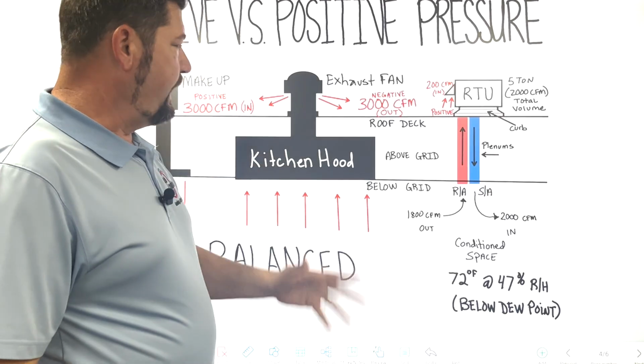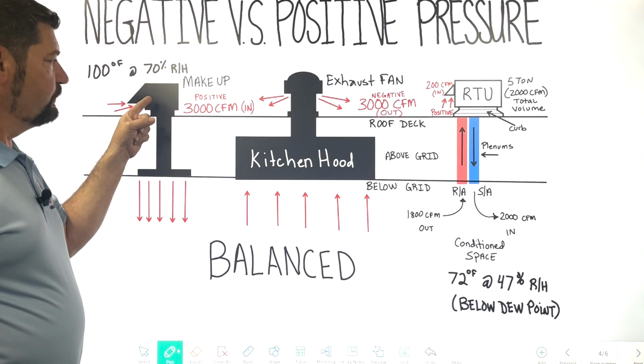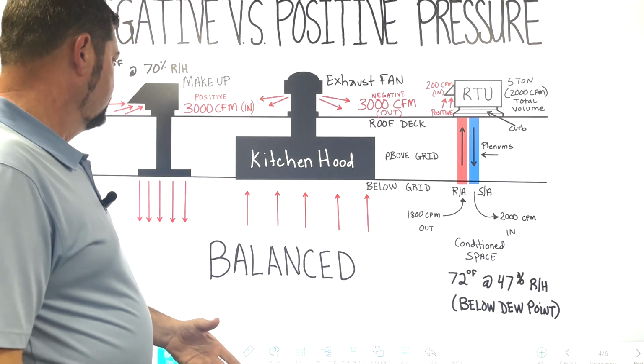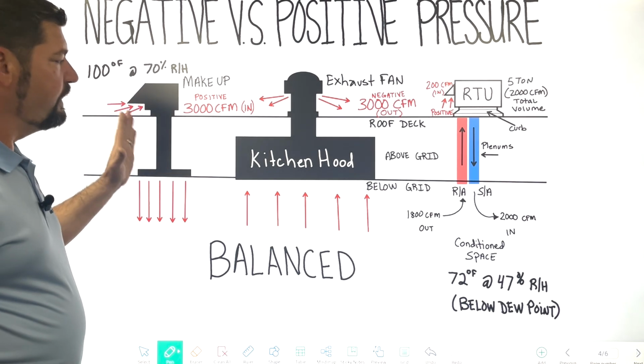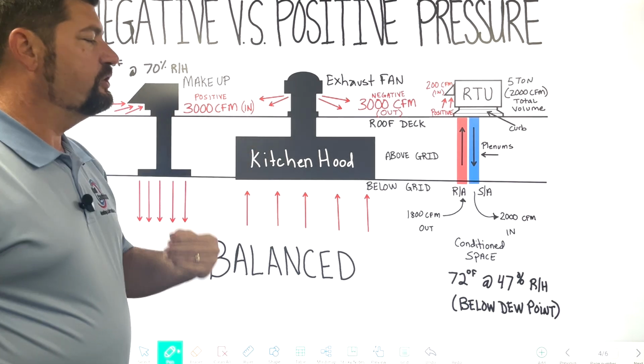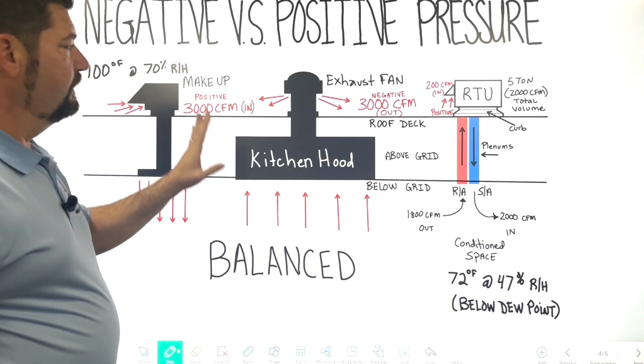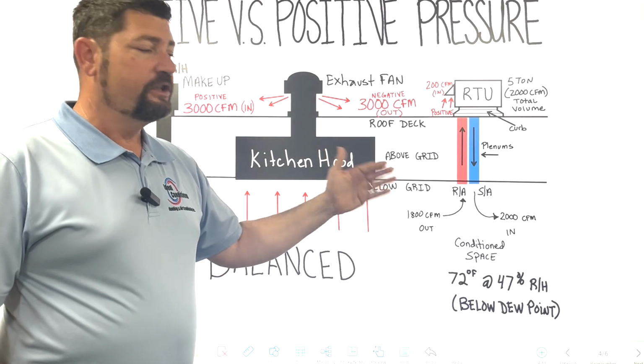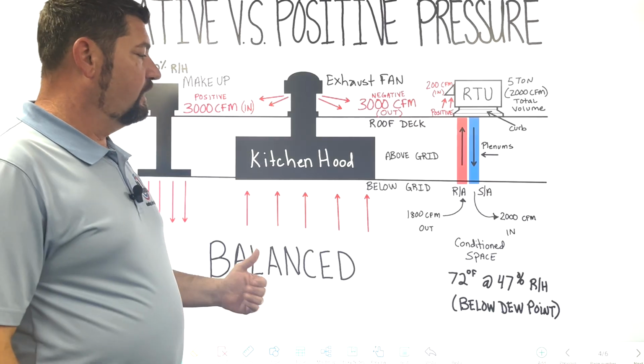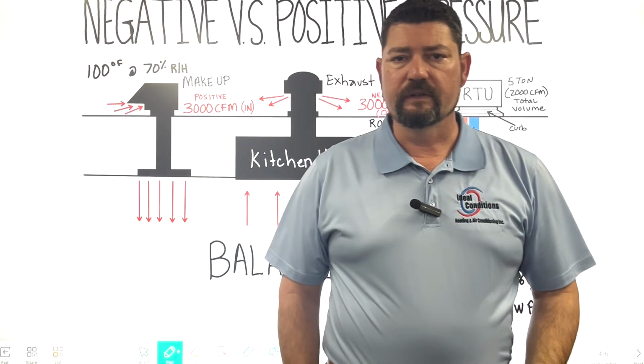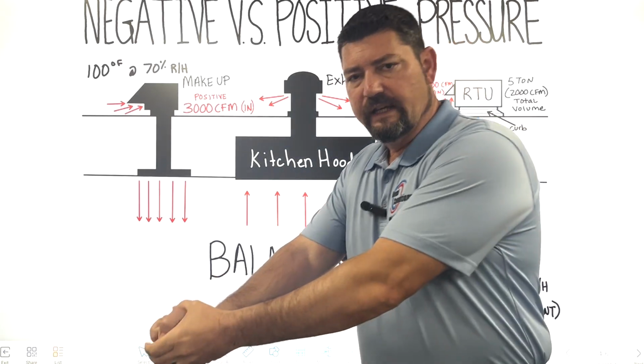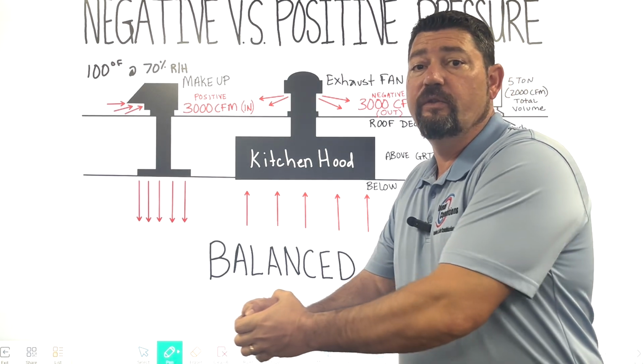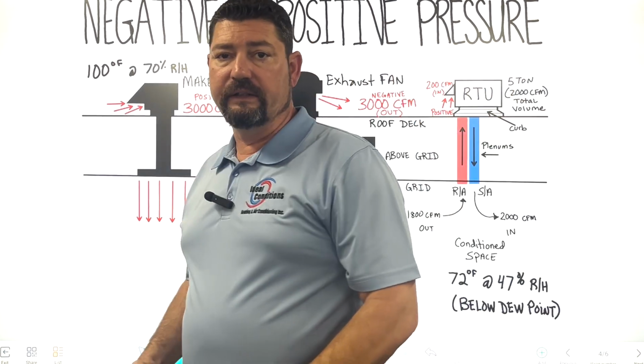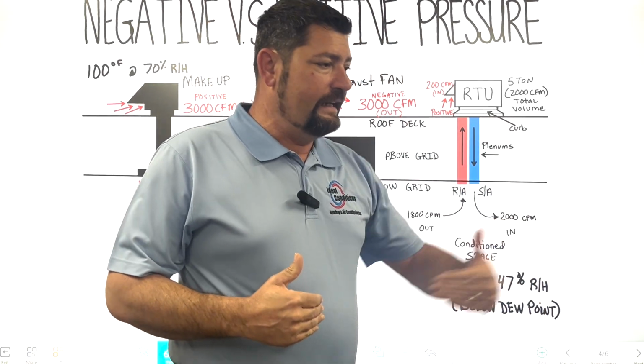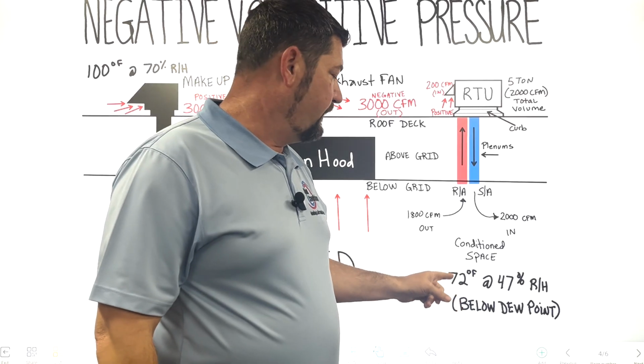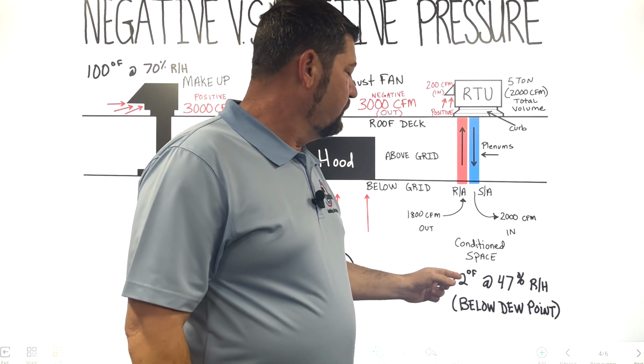Okay? What happens is these belts on these belt-driven motors, they slip, they crack, they break. When they flop off, when these motors aren't running, it could be a breaker, it could be anything. If one is running and not the other, they're going to have a problem. If the makeup air goes out, then you're pulling 3,000 CFMs out of your building. You just put the entire building in a negative pressure, right? How do you know that? Well, if you've ever gone into a restaurant and you open up the door to walk inside, and it feels like it's hard to pull that door open, it's because that negative pressure is trying to close it, right? And as soon as you pull it open, it feels like you're getting sucked into the building, right? And so that negative pressure, you're bringing in heat and humidity to a conditioned space, right? And so now that conditioned space, nothing can be going wrong over here, but now you're raising the humidity.